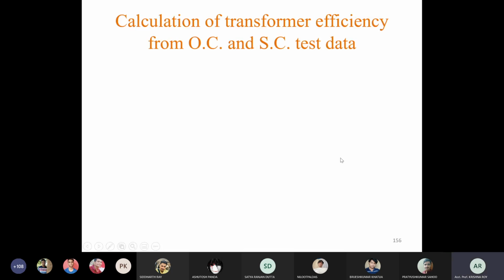Okay. Next is calculation of transformer efficiency from open circuit and short circuit test data. So how to calculate this transformer efficiency from these two test data? We only require the two wattmeter readings, nothing else. Okay, so let us see.